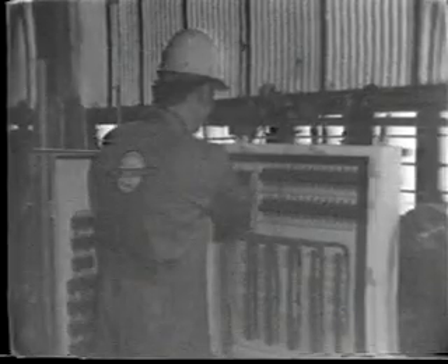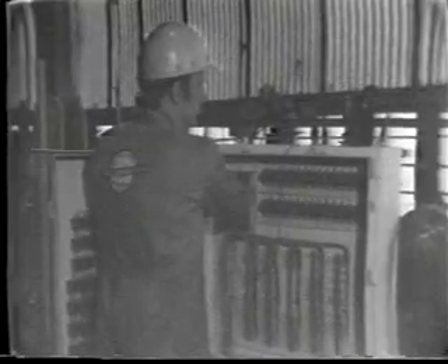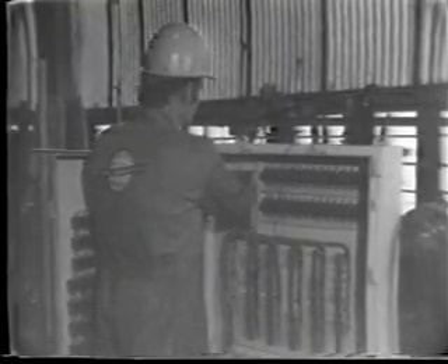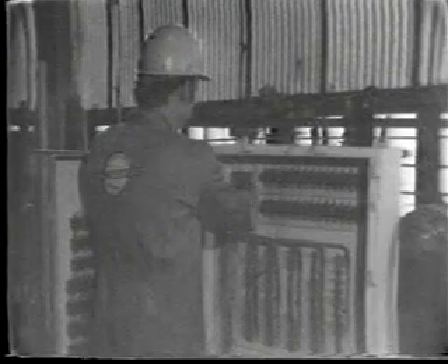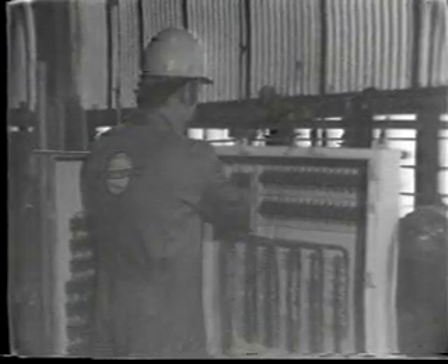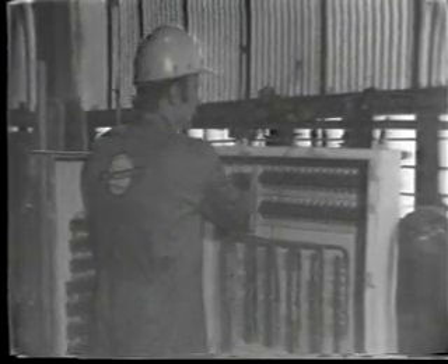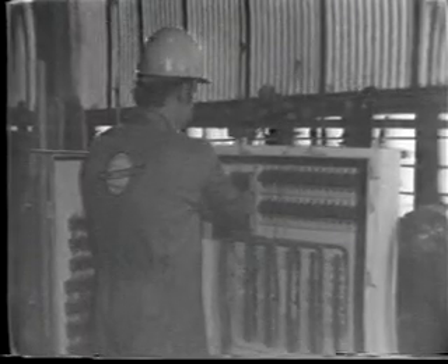First, check the schematic to find the correct relay for that function. When you find the relay, the easiest way to check it is to simply replace it with a new one. After you replace the relay, check the function again. Some memory circuits also have diodes. If your system has diodes, make certain you check these with an ohm meter to see that they are good. If the light on the panel is still not working after these procedures, then check the wiring in the memory circuit.